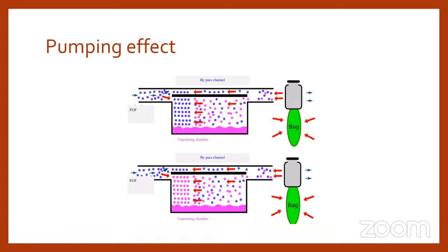Whenever we are compressing the bag, some amount of the air will be back pressure. Some amount of air will be re-entering into the system, and it causes a little bit of pressure, a little bit of pumping effect in the vaporizing chamber. Because of this pump, the vapors that are present in the vaporizing chamber will be accumulated, and it might mix with the fresh gas at the inlet end. So this is called pumping effect.